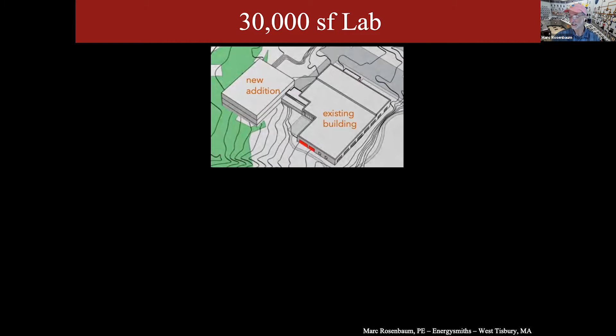His load for this addition, 30,000 square feet, is 323 tons. Now that's a lot. If you want that in kilograms, I'm going to have to do the math in my head, Allison could probably do it, but tons is a lot, and 323 tons is a lot, and 100 square feet per ton is a lot, right? So that's a really big building in terms of its size, but it's a really big building in terms of its load. And I've done buildings that are 200,000 square feet that are less than that.